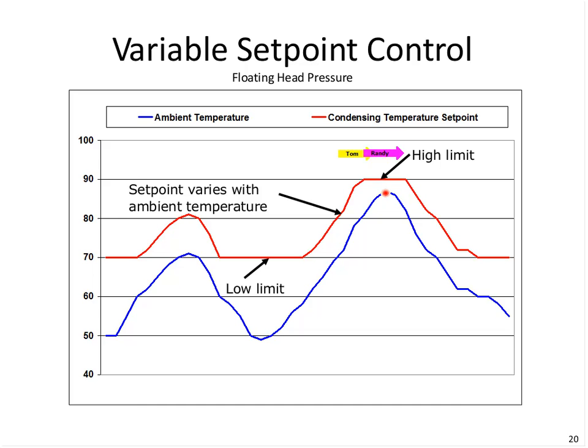I know some systems are actually incorporating a bypass in the variable frequency drive such that if we know we're going to be operating at this condition for any length of time, they actually will switch the variable frequency drive out of the fan circuit and just run it across the line at 60 hertz, really saving the drive for a milder day. Okay, well, thanks for responding to that.